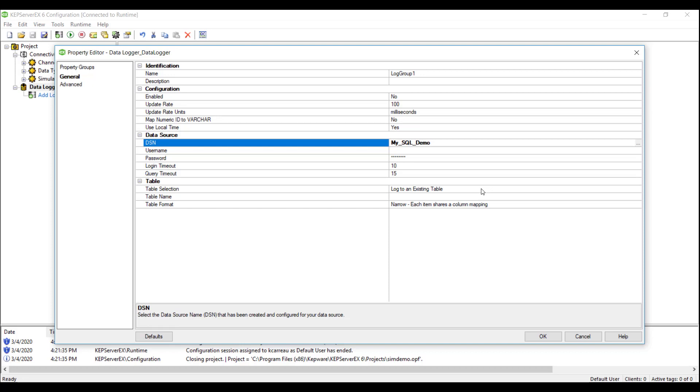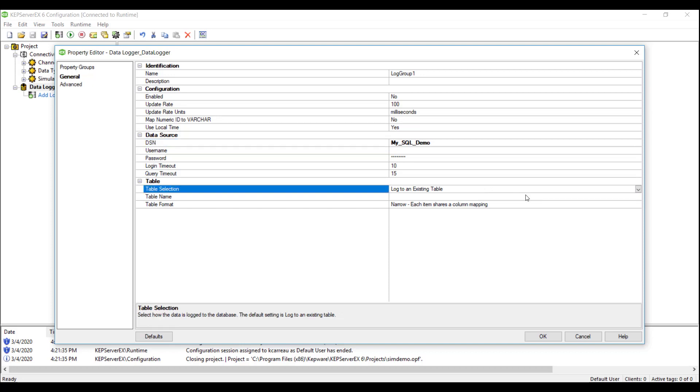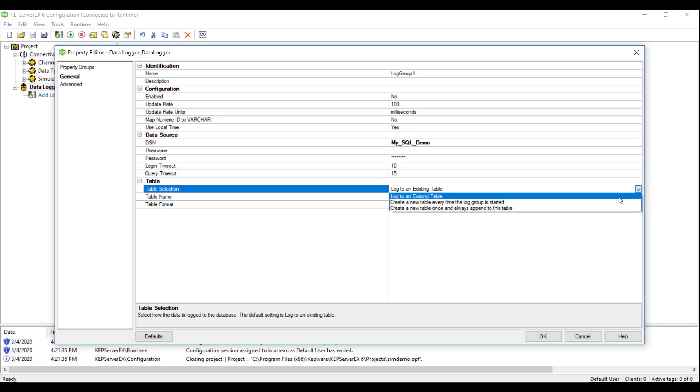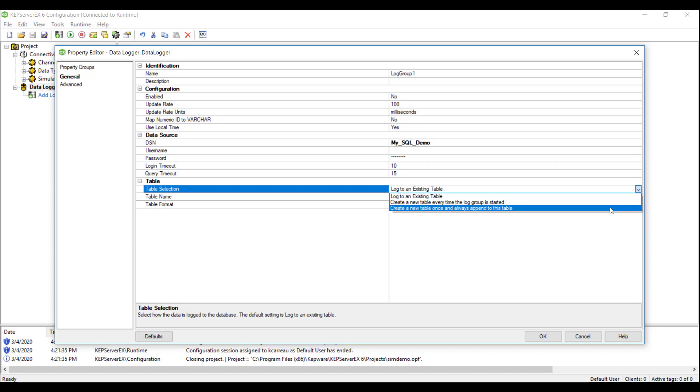Note, our DSN is using Windows authentication. If we were to use SQL authentication, we would input our credentials here. Here we have three options for Data Logger to write to a table in our database: log to an existing table, create a new table every time the log group starts collecting data, or create a table once and always append to that table.